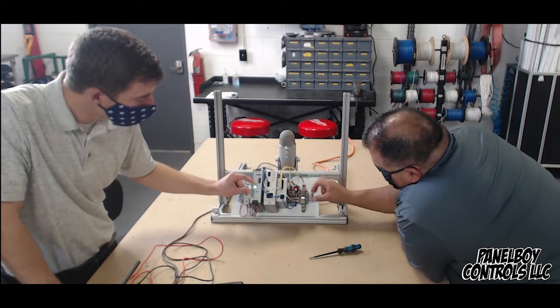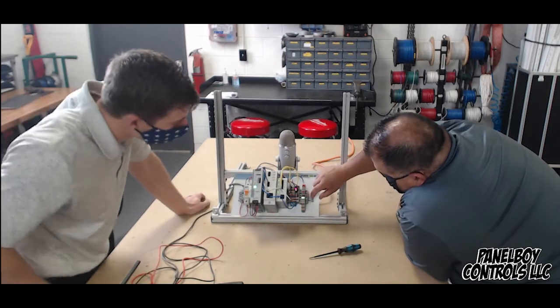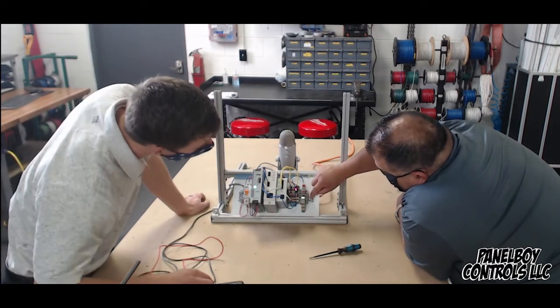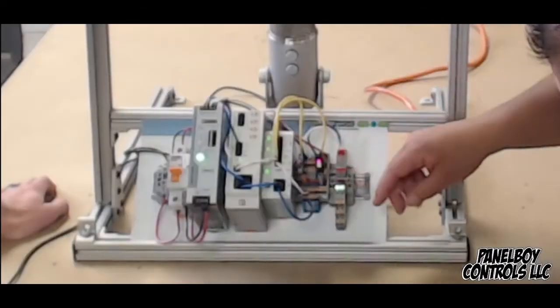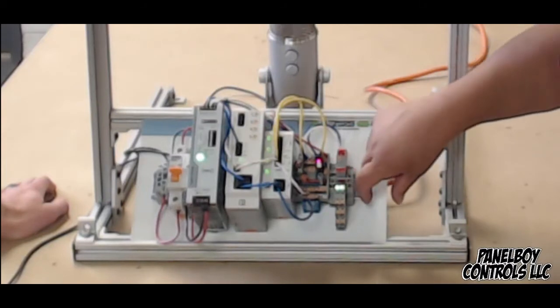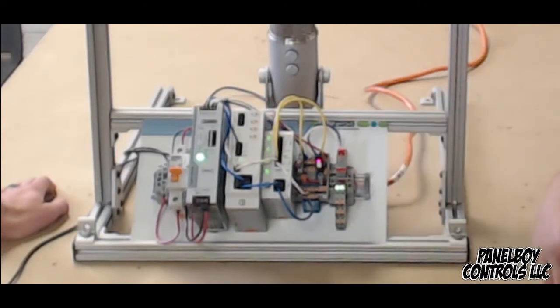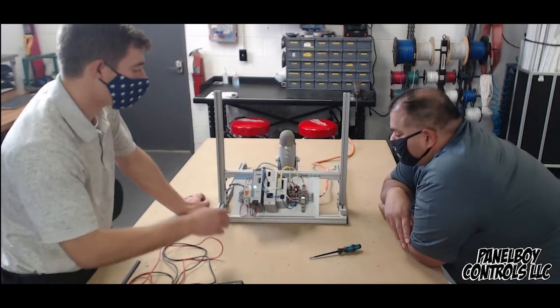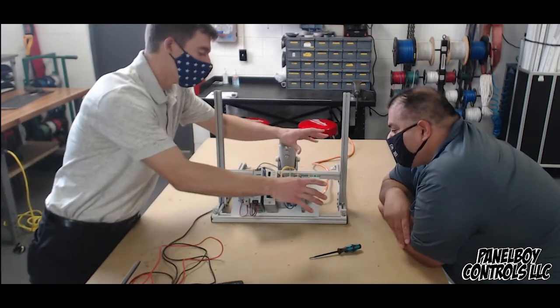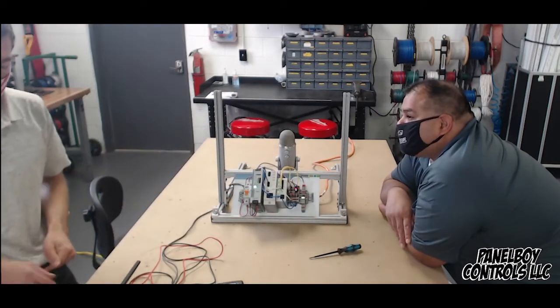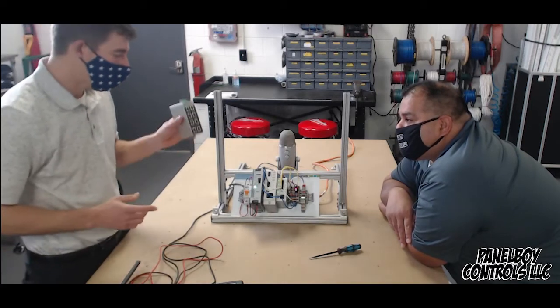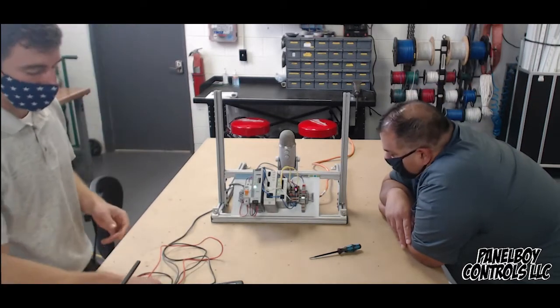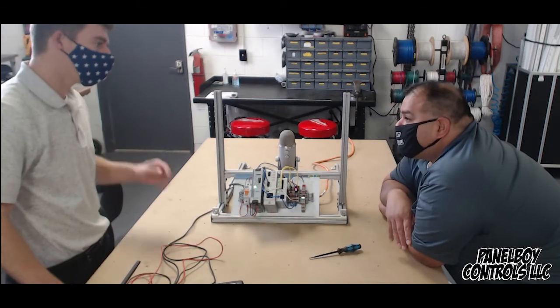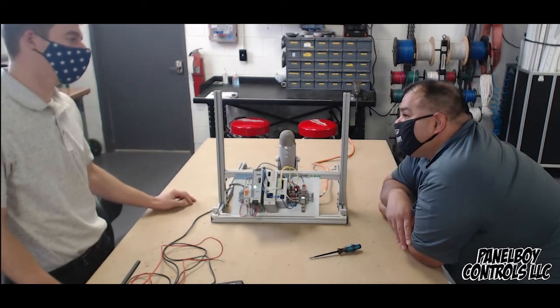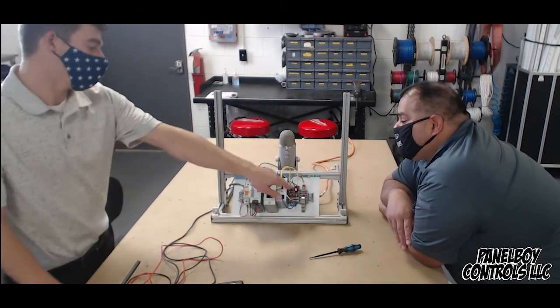So say if I put a whole bunch of terminals here and put the jumper to them. When I set this at 4 amps, will everything in this bank of terminals be protected too? Yeah, that'd be protected to 4 amps. So I can put a couple of devices out there. I could have a PLC, a couple of Ethernet switches off that, and they all run. But as soon as you get to 4 amps, you're going to start to see issues. Yep, meaning it'll trip that thing.